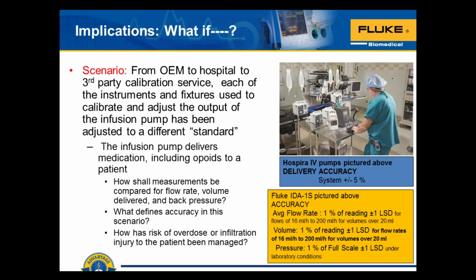And all of the answers to those questions should come from the workflow that we use, the procedure that we use to verify the performance to minimum specifications, to the manufacturer's specifications for the medical device, in this case an infusion pump, and should all be driven by our understanding of it. The accuracy that's required should be coming from those sources. The test instruments that we use and their traceability and the uncertainties that are delivered to us, we need to add our own uncertainty of measurement when we make the measurements on this particular medical device, this infusion pump.